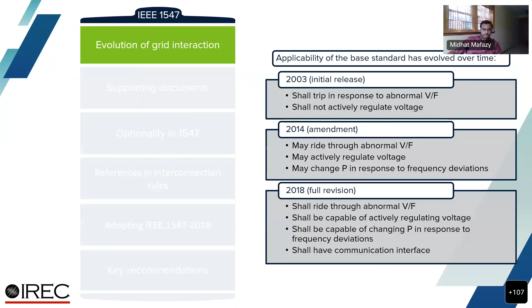Eventually, in 2018, the standard was completely revised and the technical requirements were expanded to 94 pages in the document. New requirements include ride-through, voltage and frequency regulation to support the grid, as well as supporting communications and control in a standardized manner. As shown in the slide, such smart requirements are referred to with the word shall. Next slide.